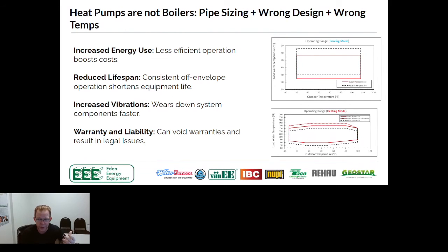The other thing about these units is it's like anything. If it doesn't sound right, it's probably not right. If I walk into a mechanical room and I can hear your heat pump running, not a good sign. If you have an air to water, it's probably outside, same conversation. If I'm standing next to my IBC air to water or the System M air to water or the Enertech, because we have all three installed, you can't hear them running. Like you can hear them, but you don't hear the compressor, you hear the fan. They're designed to be very, very quiet. So it'll be much louder.